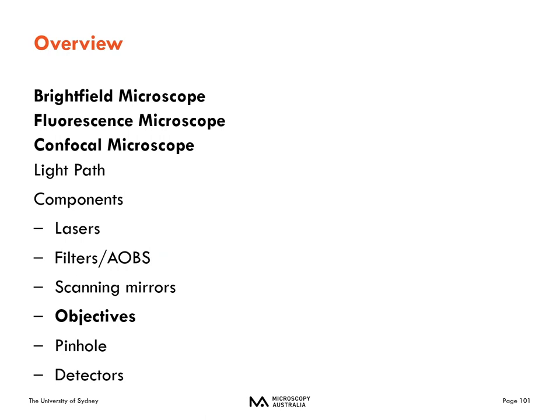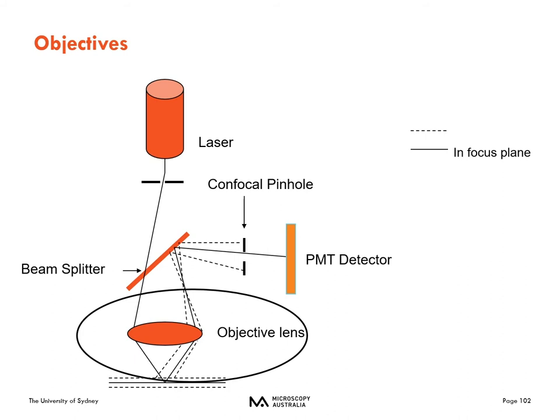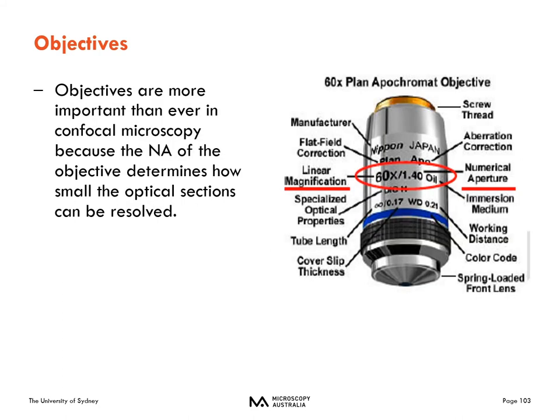We've now talked about lasers, filters, and scanning. Now I'm going to talk more about objectives. Just like in fluorescence and brightfield microscopy, the objective lens is probably the most important part of your microscope. In confocal microscopy, you really need to think hard about that numerical aperture — I just talked about sampling and resolution, and that comes back to numerical aperture. Something we think about in confocal microscopy is optical sectioning, the z-depth of each slice. The numerical aperture determines how thick that optical section is going to be.